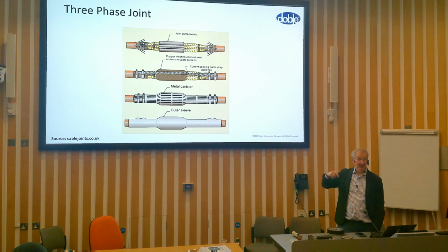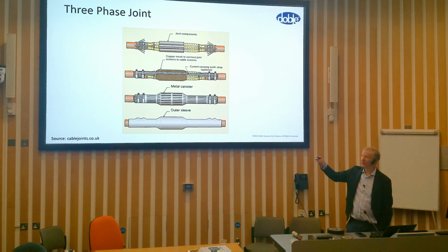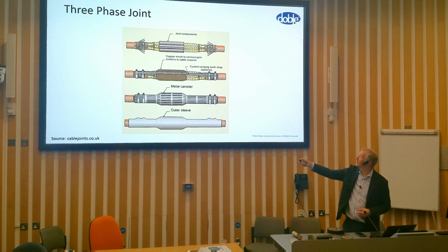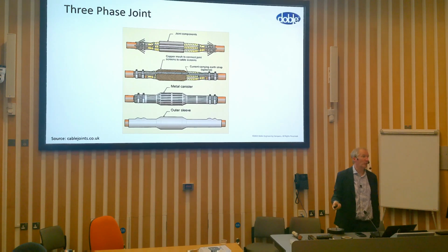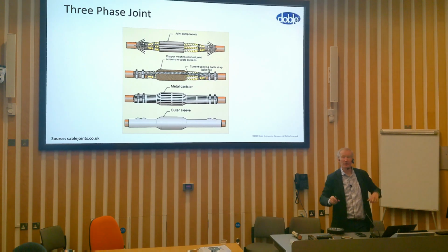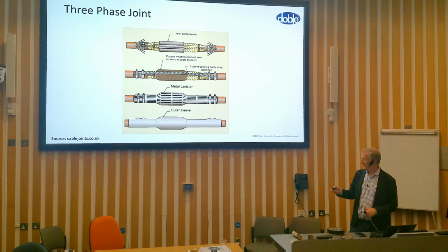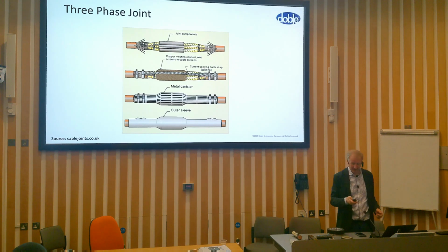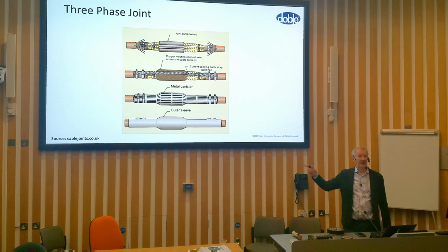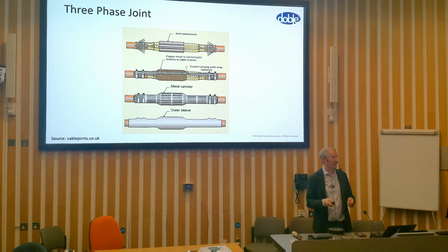Thinking back to how they make the joints: the 3-core cable has 3 smaller cables inside each big cable. You joint each individual phase to the one on the other side. You put some protection, like wire mesh, for continuity over the joint. You've got a braid to carry fault current - a big thick metal ribbon - and then some kind of protection on the outside to keep out moisture and contamination. That's the order you'd make the joint in if you were doing it in the field.